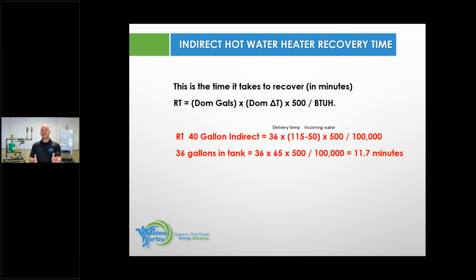That's part of our universal hydronic formula. So it's 36, the size of my tank. I'm going to multiply that by 65, multiply that by 500, and divide that by 100,000. That tells me, on 50-degree water coming in, to get my tank up to 115 degrees to be ready to support the home, that should take 11.7 minutes with a 100,000 BTU boiler.